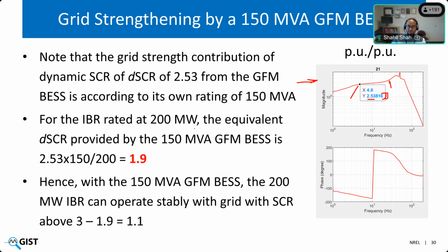Now, for a 200 megawatt IBR, that same 2.5 would be 1.9. So this implies that if I connect this 150 MVA BESS at the POI of that 200 megawatt IBR, the BESS would contribute dynamic grid strength equivalent to what a grid with an SCR of 1.9 would contribute. So what this should mean is that the 200 megawatt IBR should remain stable if the grid's short circuit ratio is around 3 minus 1.9, or basically around 1.1.